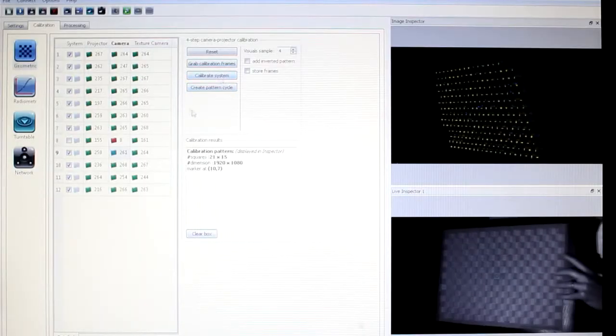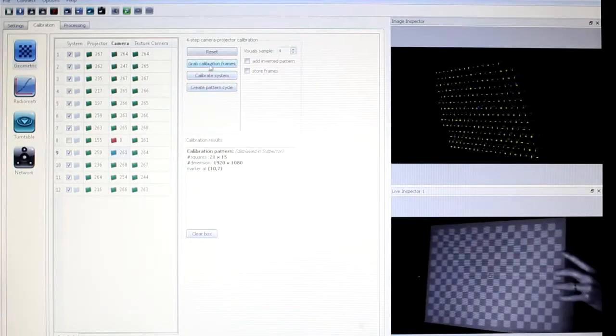When you have captured between 5 and 12 images and unticked any bad ones, click the button Calibrate System. It may take a couple of minutes to analyze the information collected, depending on the speed of your PC. We're looking to get an RMS value of between 0.2 and 0.6.